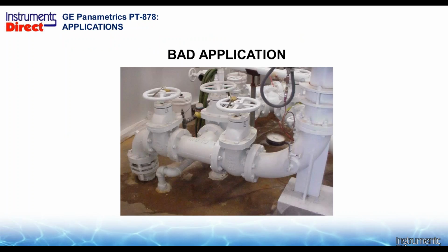So as far as the application itself, this is what usually happens on Monday morning. I get in the car and I drive 200 miles to do a flow survey, and I get there and this is the plumbing I have to work with. And they'll say, just put your flow sensor right here. Well, we've all had this experience, and the answer is don't put your flow sensor there because you're not going to get anything. Rule of thumb in showing the performance of an ultrasonic flow meter: never show it working or not working on purpose. It leaves a stigma, so your end client or end user is going to look at that and say, well, I just want to see it work. I know it's not a good application. This is an application where you would decline to put the meter on the pipe because it ain't going to work.